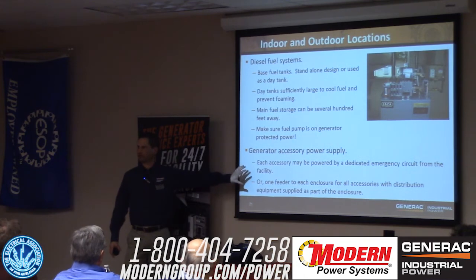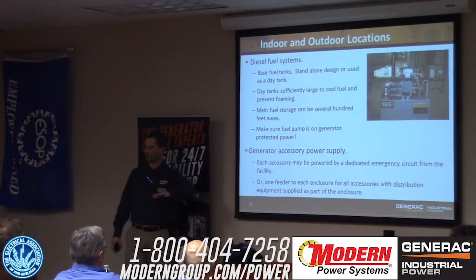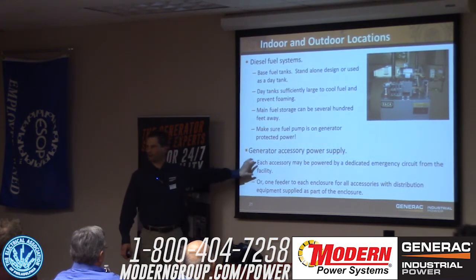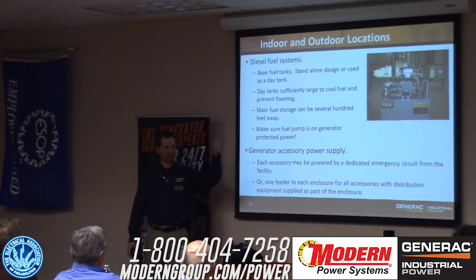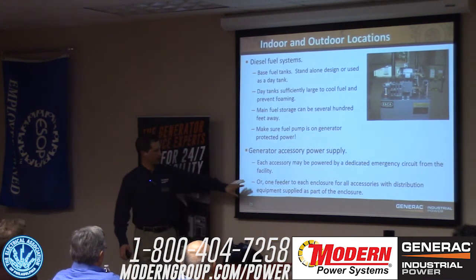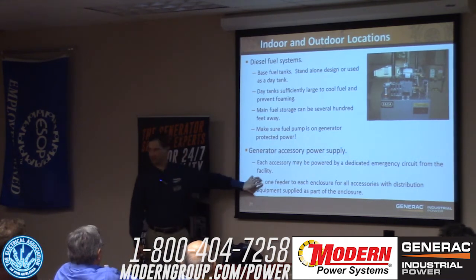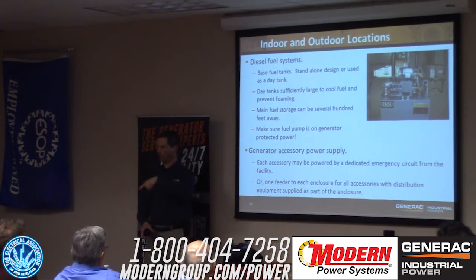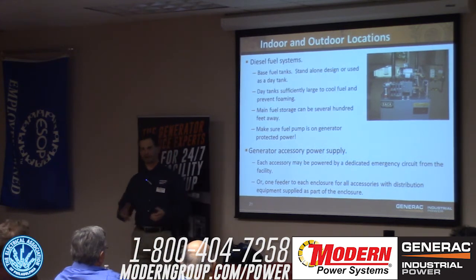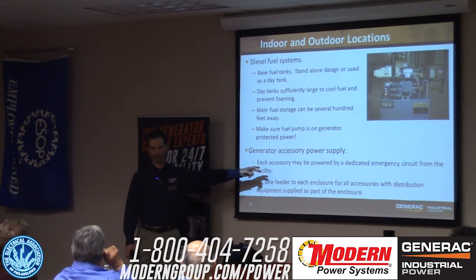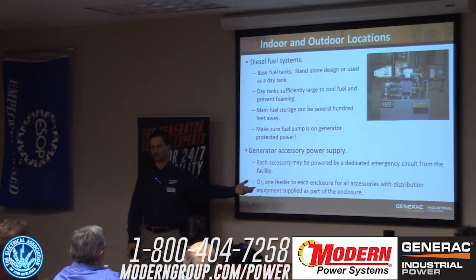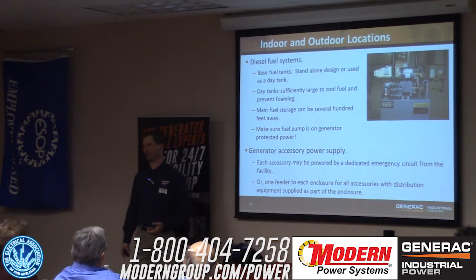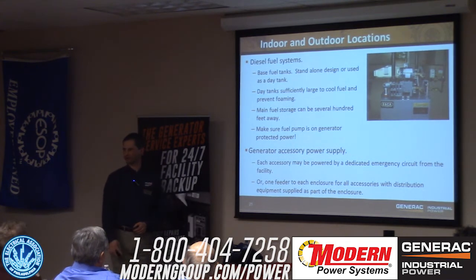When you're doing your accessory supply power outside, this varies based on the genset. Some engineers want a separate accessory power run for the battery charger, the block heater, the enclosure heater, whatever. But a lot of manufacturers, including us, will put a little sub panel out there in the genset, so it's one feeder for you to pull. It has to be sized appropriately, saves you time in labor, and you don't have to figure out where everything goes on the terminal strips, what's 120, what's 240. Just pull a 240 or 208 volt, 2-pole circuit out there, sized appropriately for the genset and heaters. That'll all be provided to you, and it saves a lot of aggravation and time on site.